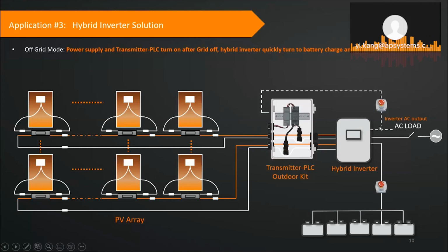And by doing that design, you will be able to let your PV array stay alive even when the grid is off. Sometimes the AHJ will request additional control during the wiring from outside. So they will be able to control your system, maybe just by a single safety switch. Something like that. Yeah.